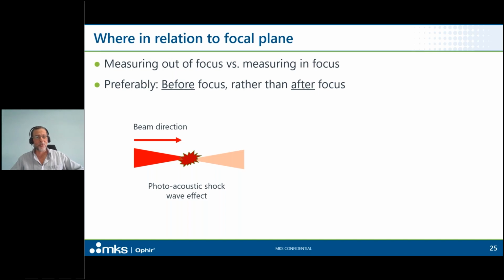Tell me that's not cool. In the real application, that won't happen, because in the real application, the beam doesn't continue past the focal spot because that's where the patient is. But if I'm going to measure the beam, I want to measure here, not here, because here I have a more accurate representation of the power in the beam. Here, I've lost some of that power sometimes.